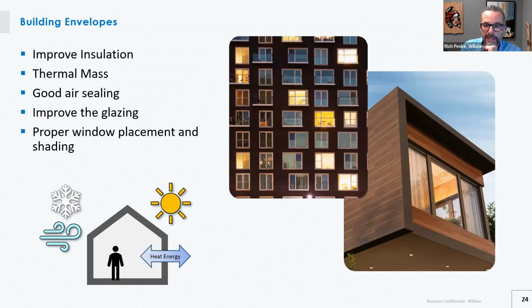The building envelope is a key focus for any efficiency goal. Without a good envelope, you'll need a bigger mechanical system just to make up for it, and that poor building is going to spend the rest of its life fighting harder than it had to just to not waste energy. So insulation, thermal mass, air sealing, those things are now in codes. Not just the air barrier, but testing it now to make sure it's doing what it's supposed to. And this is where you as architects can really make a difference through detailing all of those openings, so that air tightness isn't relying on whatever the contractors felt like doing that day.